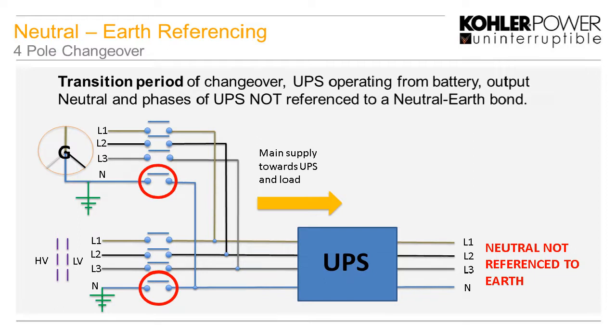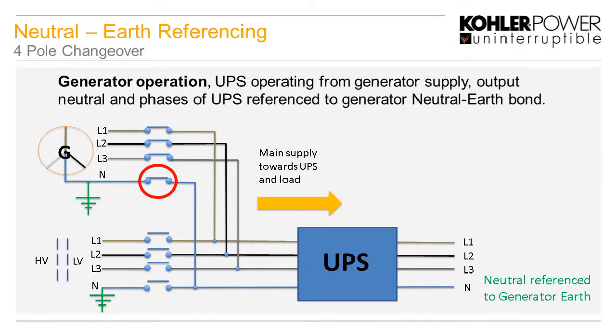If we want a neutral earth bond at the UPS or after the UPS, we have to do something about that, irrelevant of what kind of UPS it is. And that's very important to consider. Once we're onto generator, that neutral is now bonded to the star point and to the earth at the generator. So the output of the UPS neutral is now referenced to that generator earth. And obviously, we're back into a safe condition.